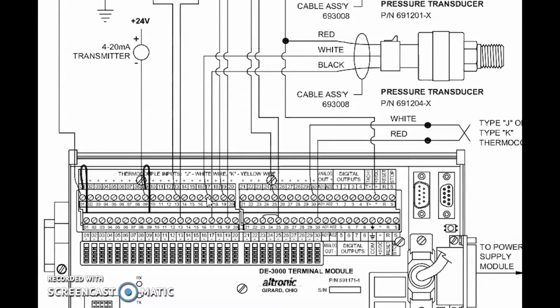But as we know, sometimes the pressures drift a little bit or the voltages drift a little bit, and they need calibration from time to time to maintain their accuracy over the life of the pressure transducer. Now, before we get started on actually walking you through a procedure on how to calibrate the pressure transducer, I want to be real clear on something. If we have a pressure transducer that is constantly getting out of calibration, meaning it's calibrated one day and the next day it's off again, more than likely we have a damaged pressure transducer.